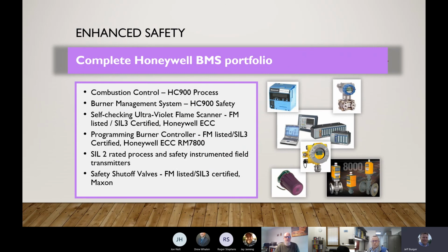So last but not least, we've talked a lot about enhanced safety. The HC900 is really used in a lot of different applications for enhanced safety. As I stated earlier, it's used a lot in burner management systems with combustion systems. Also, outside of the HC900, there's a whole lot of other Honeywell control products that offer that enhanced level of safety as well. Up in the top left here, this little blue box is an RM7800 series that offers a SIL-rated burner management system, flame safeguard system. You move over to the right-hand side, you have this Honeywell transmitter that also has a SIL rating for doing pressure, flow, level type applications. Obviously, HC900, which is the star of the show today, has a SIL 2 rating.